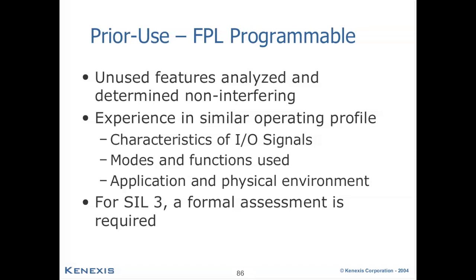Your prior use requirements may also vary on the programming language that is required for the given device, whether it be a programmable piece of equipment with fixed programming language or limited variability language. In the case of FPL programmable components, you'll want to ensure that the unused features of the components are analyzed and determined to be non-interfering with respect to the device being able to perform the required safety action.